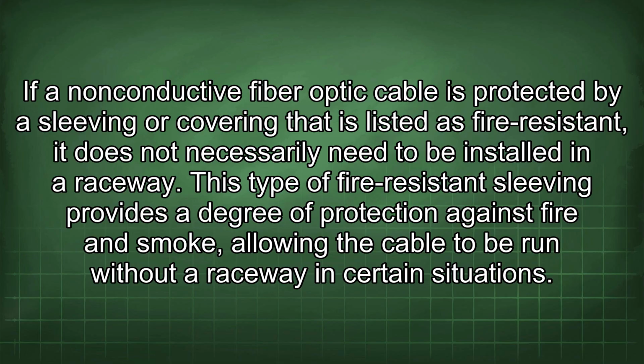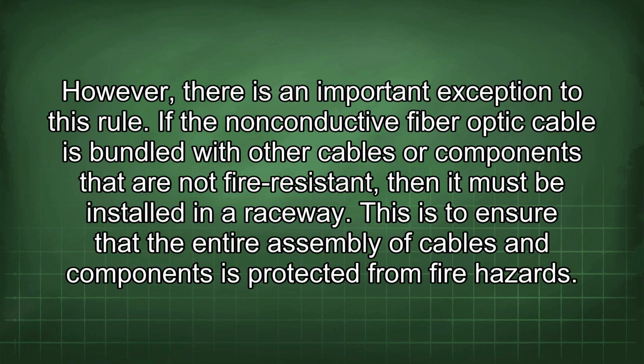If a non-conductive fiber optic cable is protected by a sleeving or covering that is listed as fire-resistant, it does not necessarily need to be installed in a raceway. This type of fire-resistant sleeving provides a degree of protection against fire and smoke, allowing the cable to be run without a raceway in certain situations. However, there is an important exception to this rule. If the non-conductive fiber optic cable is bundled with other cables or components that are not fire-resistant, then it must be installed in a raceway.